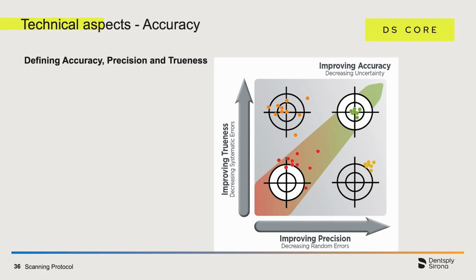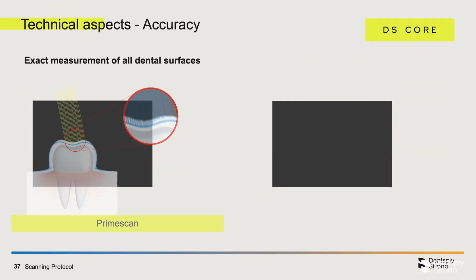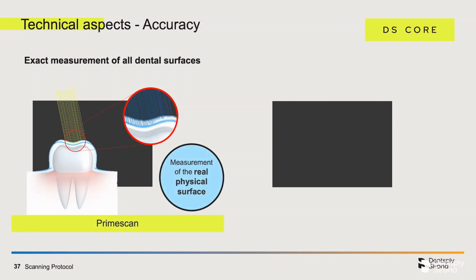The definition of accuracy, trueness, and precision. Accuracy is defined as a combination of trueness and precision. Here, precision means achieving a result that is as consistent as possible without a large spread. In contrast, trueness means a position in the target area that is as correct as possible. Both together, that is, a small range of variation with the most correct detection of the correct value possible, means accuracy in the end. The Primescan enables the detection of all real physical surfaces.